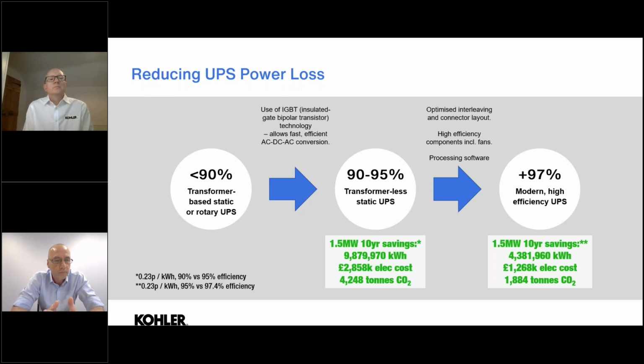So what's been done to increase the efficiency and sustainability with UPSs? Now, over the years, the UPS designs have changed. Early days, we had transformer-based static or rotary UPSs, and their efficiency was quite often a lot less than 90%. Now, with the evolution of IGBTs, transistors, it allowed us to increase the switching technology, and therefore we were getting 95% going forward, and that was really increased once we got to the transformerless static UPSs, pushing those bandwidths higher up towards the 95%.